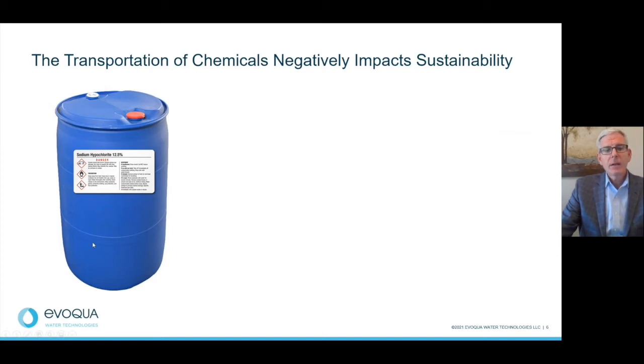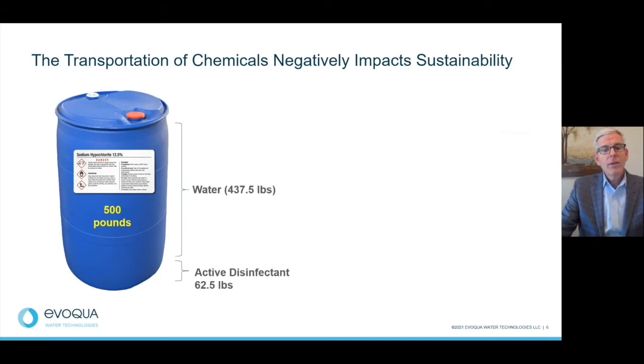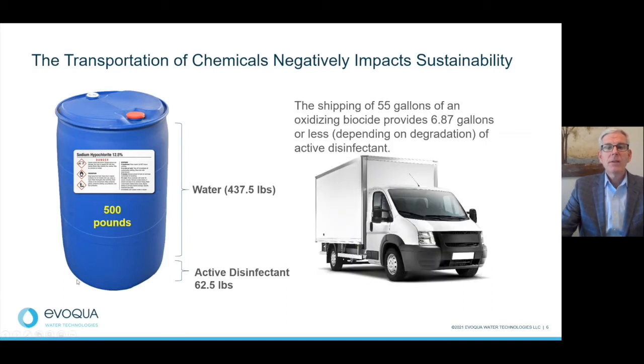Now, a 55-gallon drum of sodium hypochlorite weighs about 500 pounds. And of that 500 pounds, roughly 437 is water. So what this means is that you're transporting 55 gallons of a product to get less than 7 gallons of the active ingredient that is helping to disinfect your water. I hope you can see that this is not a good equation when it comes to the relationship of carbon produced to transport the active portion of this chemical.